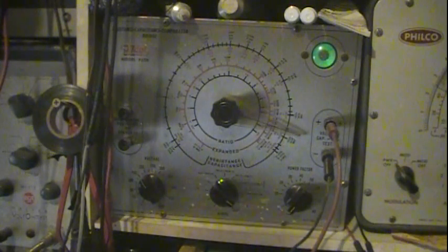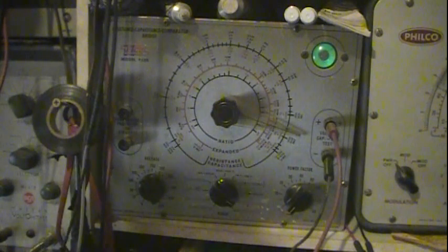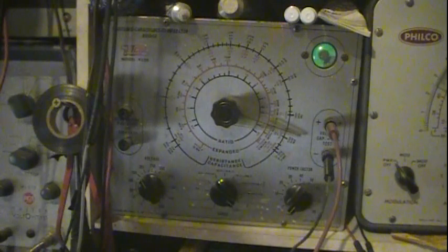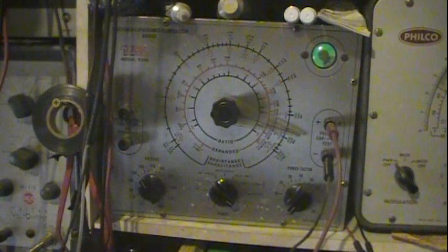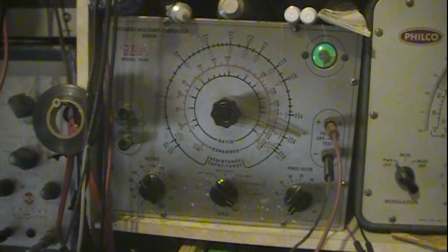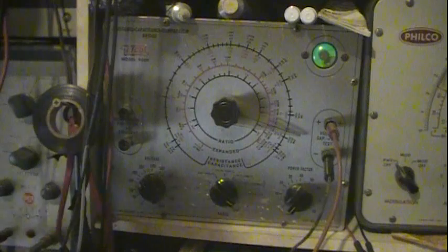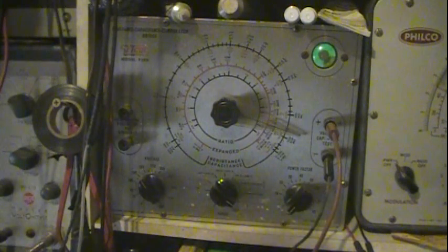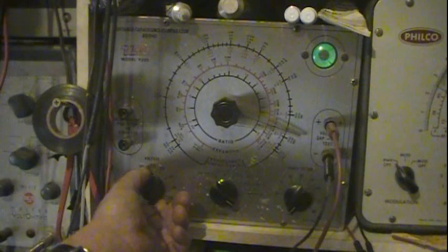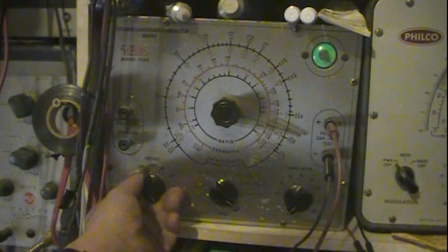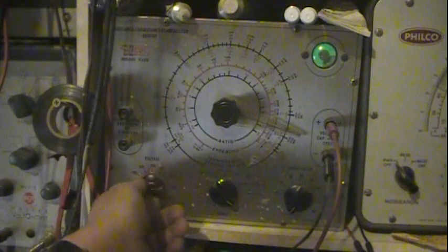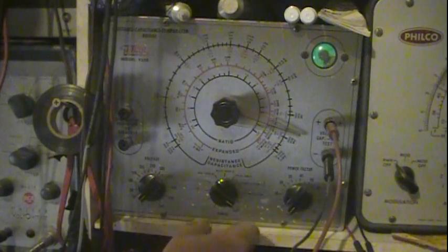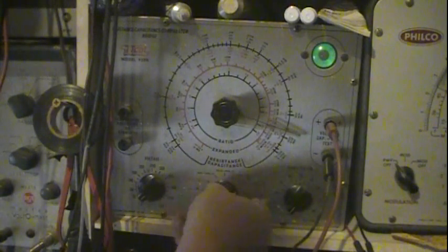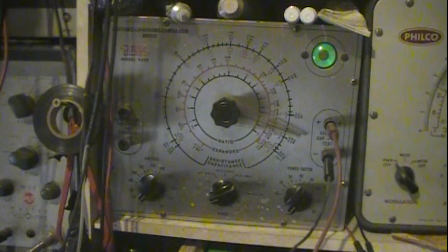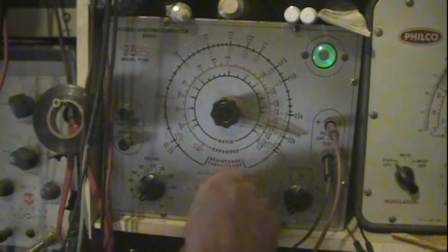Now, just to be on the safe side here, I can go back and check those others. Aha. The meter's showing leakage. So we'll quickly run through the others just to double check them. Our meter is actually causing leakage because these are highly sensitive, so keeping the meter in there is probably not the best way of doing it. Let's just double check real quick and see what some of these are actually doing.